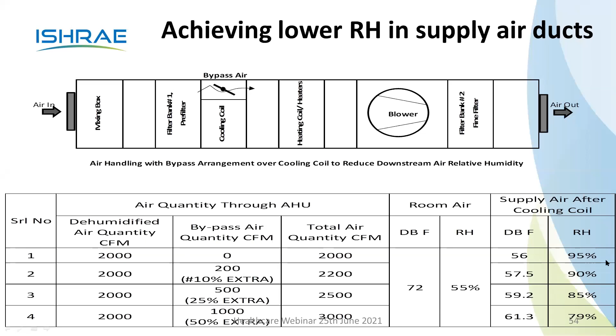So what is done is, suppose you have 2000 CFM and that is the dehumidified air quantity, you have got zero bypass. Let us say your ADP is 56 Fahrenheit, then the RH downstream will be 95%. If you take certain amount of bypass, 200, you can get it down to 90%. Similarly, by increasing bypass to certain extent, say you are making it 25% of the bypass, you are able to get it to 85%. So the point is that you should not have just the dehumidified air going down the supply duct. There has to be certain amount of bypass air so that you don't have mold formation in the downstream filters, that is filter bank 2, and the supply ducts.